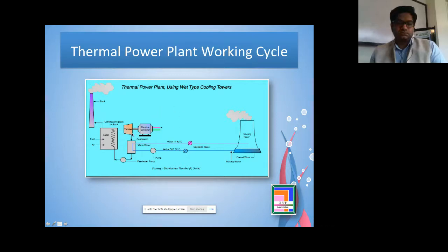So now once the steam comes out, it is at a very low pressure. It is at almost 0.6 bar. Sometimes it depends on the kind of turbine and manufacturer. Different manufacturers have different designs and different amounts of energy being utilized there. So they almost all get 0.3 to 0.6 bar as steam pressure, but the temperature is almost all like 60 degrees centigrade.